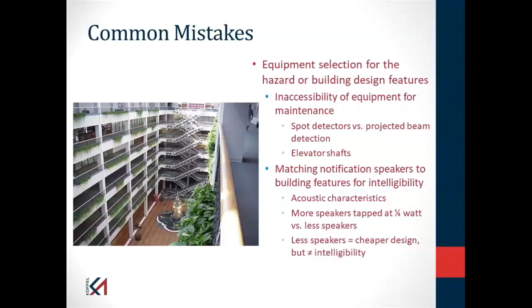Okay. Today, there's increased emphasis on intelligibility of the fire alarm system. For many of you, if you have a voice communication system, you might have an announcement that sounds something like, you can't understand it. Now, I know it's a fire because I see lights flashing and I heard that alert tone, so I respond to it as a fire signal. But today in many buildings, because we might not want everybody to evacuate, we need intelligibility. One of the key aspects to intelligibility is actually more devices tapped at a lower power setting to have a more equal sound distribution, and that will significantly increase intelligibility. NFPA 72 says it's up to the design team to determine what's referred to as acoustically distinguishable spaces, those spaces where intelligibility is an issue.